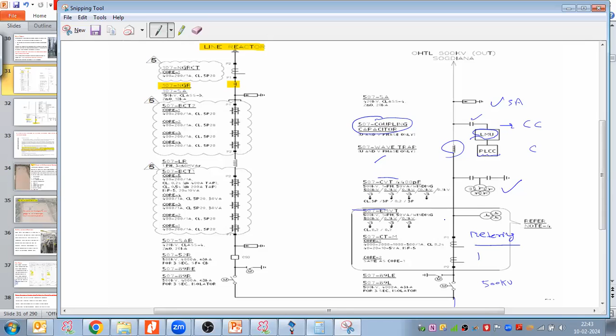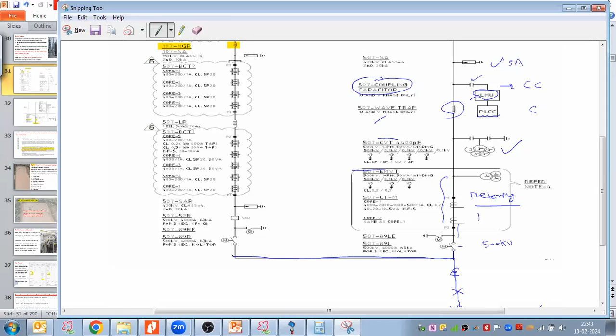And then we have the CVT, which is utilized for the metering and protection purpose. Then I have dedicated metering CT and VT for the energy metering or tariff metering of this particular dedicated feeder. Due to that reason, this EMVT and the CT is coming here. I will take this part separately. And then I have the disconnectors here. This earthing switch is for the line maintenance, and here I have a disconnector.